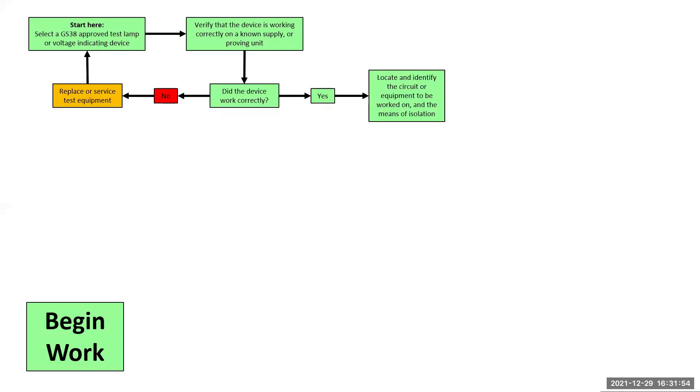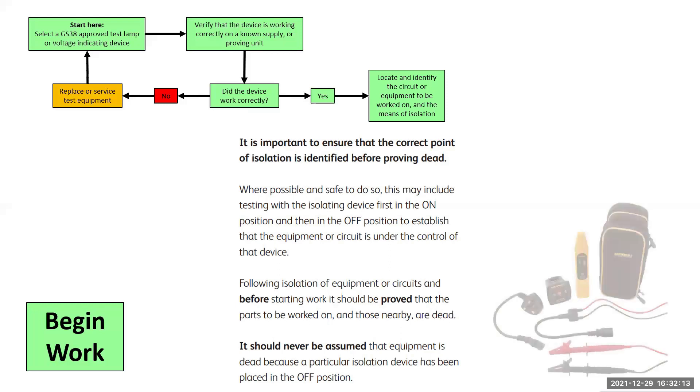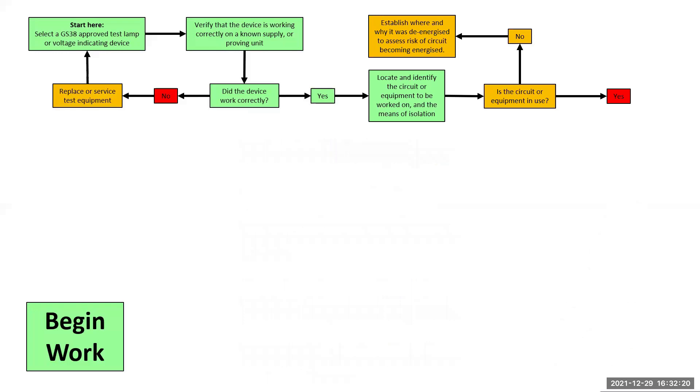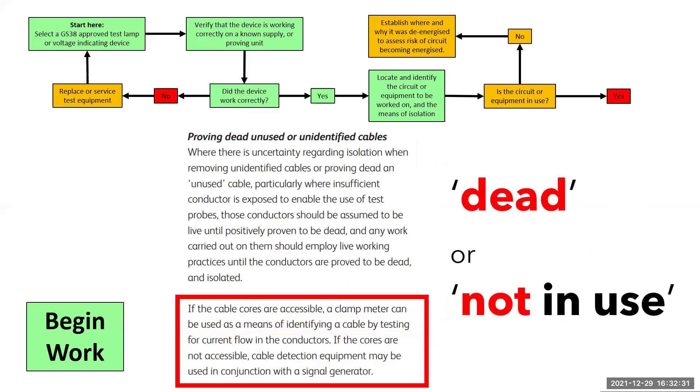Next, we locate the circuit or equipment to be worked on, as well as the point of isolation. The guidance from the best practice guide is to prove that the equipment is actually controlled by the isolation device and not just to assume that this is the case. You can do that by operating light switches or plugging in a socket tester. But the best way is to use a circuit finder, like the one pictured here, which costs around £100. If you come across an unknown circuit, you must assume that the cable is live until proven otherwise, even if it is marked up as dead or not in use. The best practice guide suggests that a clamp meter can be a means of identifying a cable, but that will only work if current is flowing.